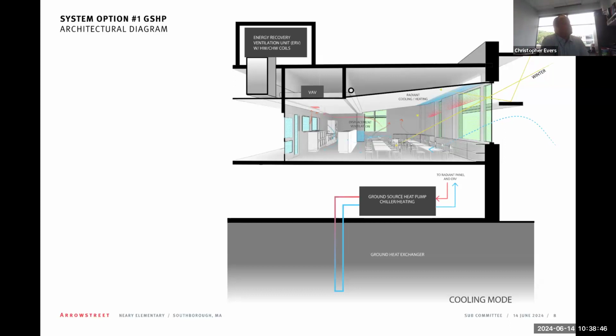I think, with a system that has some infrastructure with piping, you're already going to do the ductwork no matter what. You have to bring ventilation and fresh air to the classrooms and spaces. So I think our best option would be to look at a system that has piping infrastructure, especially if you're doing water source on the terminal boxes as well. Are you reheating the air with VAVs with hot water coils, or would it be electric, because you're running the distribution?